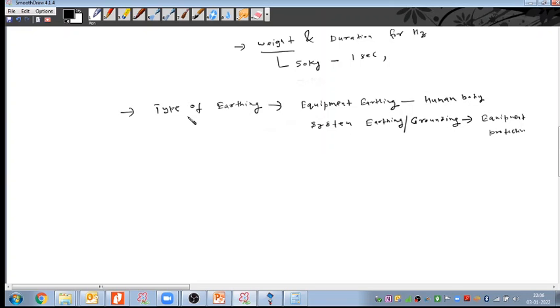Generally, we do not take line to ground. Generally, we take the highest fault, how much highest fault may come on the system, and based on that we design the system. But at that site it was a challenge due to the highest resistivity. That's why we went with this kind of alternative, considering only the line to ground fault current. I'm sharing this example so that when you face this kind of issue, you can go with the line to ground fault current in the entire system calculations.